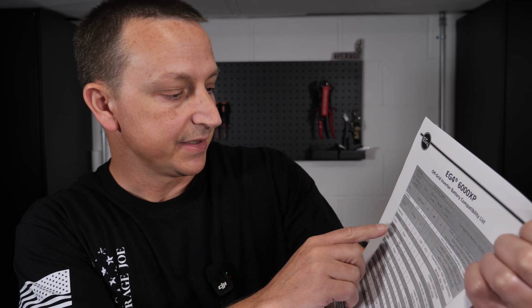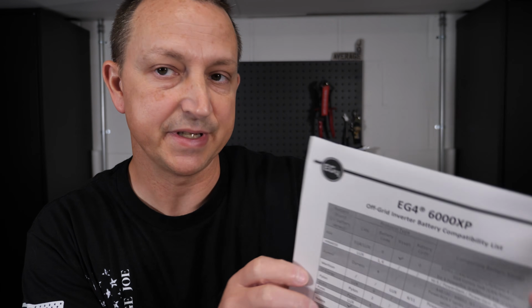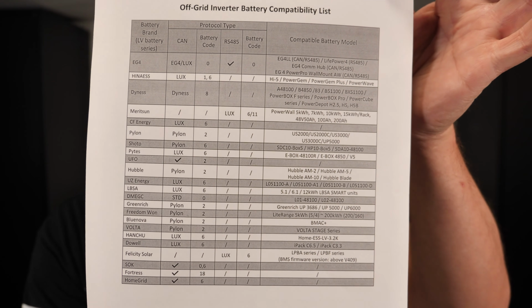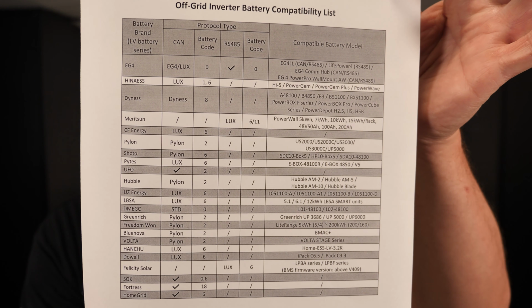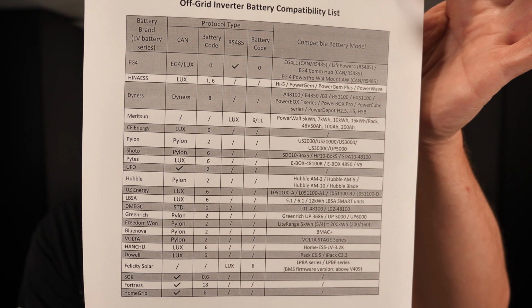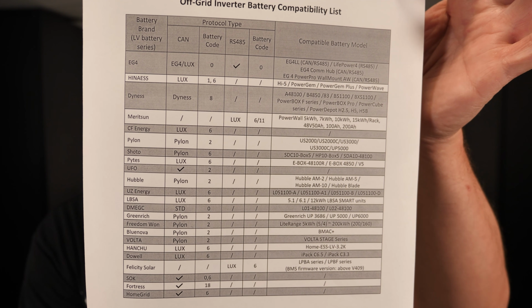and that kind of goes with their Lux Power version, or since we are using a Lux Power inverter, it says to use option 6 or protocol 6. So I'm just going to hold these right here for just a second. You can take a look at those if you would like, but mainly we're focused on protocol 0 or protocol 6. And then inside the battery, I hooked up the RS-232, and we can see what the batteries are set on. Right now, those are set on the Pylon Tech, which is the protocol for the EG4 Lux Power inverters. Okay, so that's basically what we're gonna do.